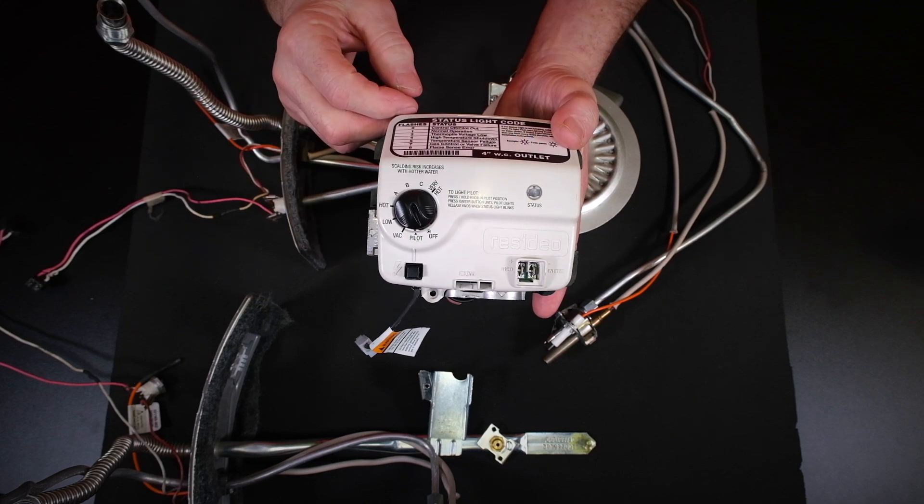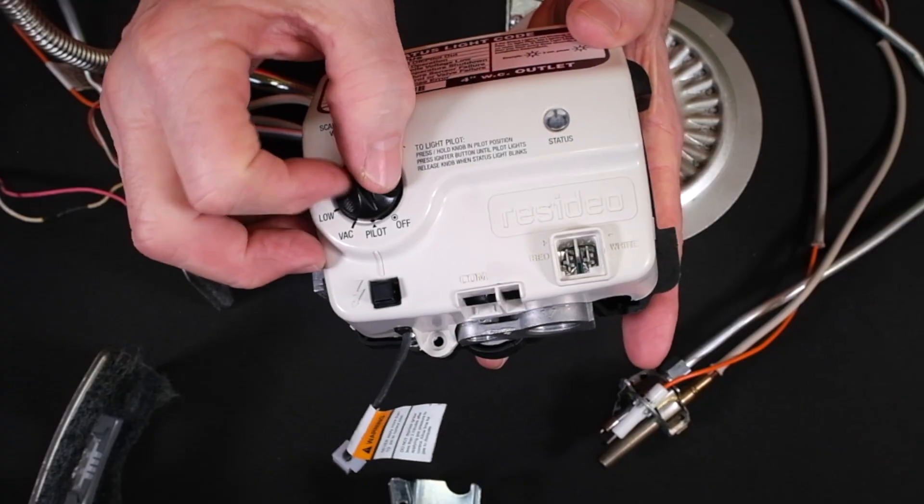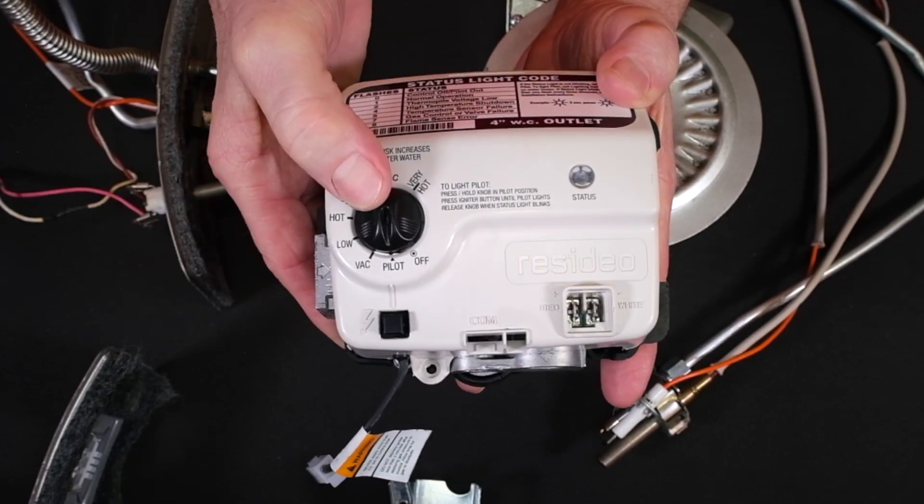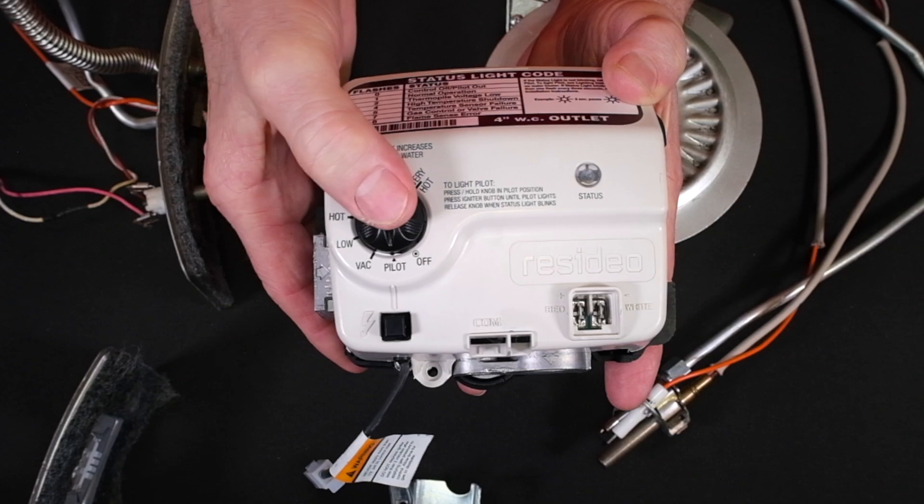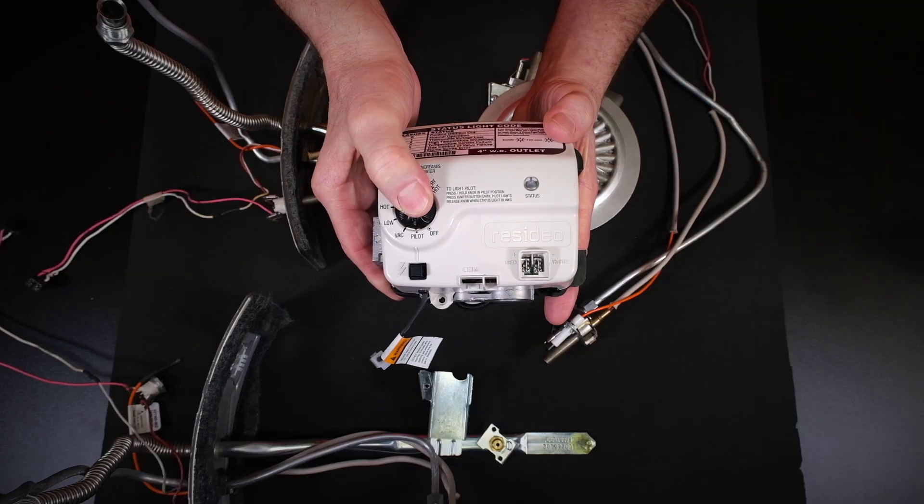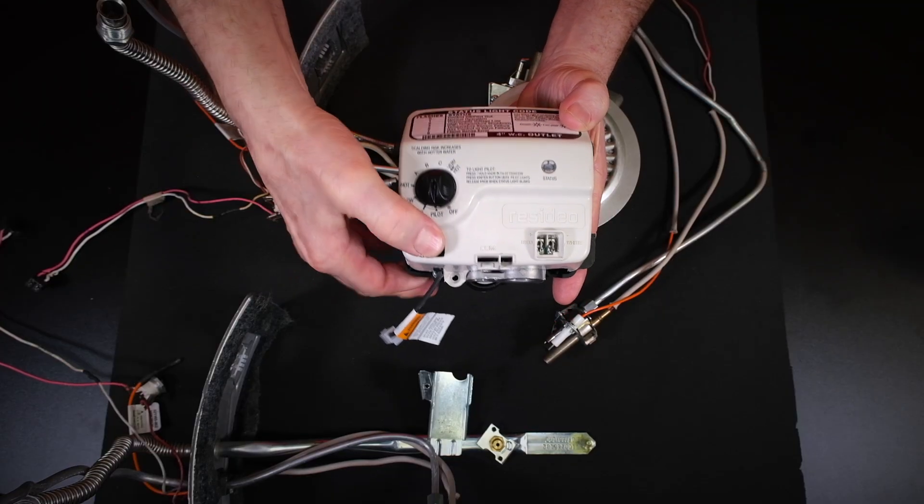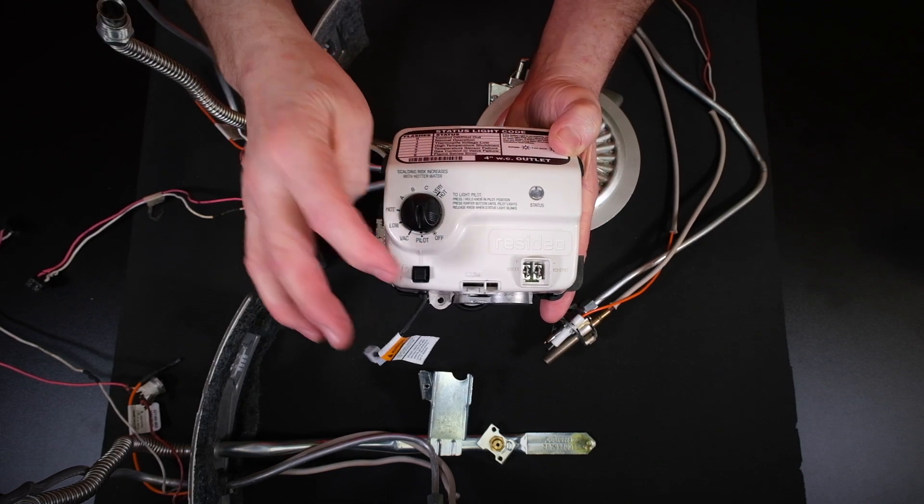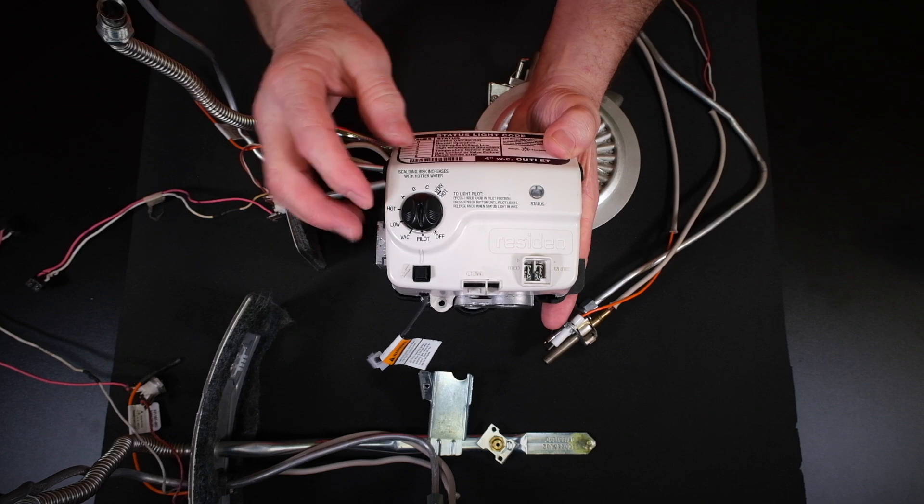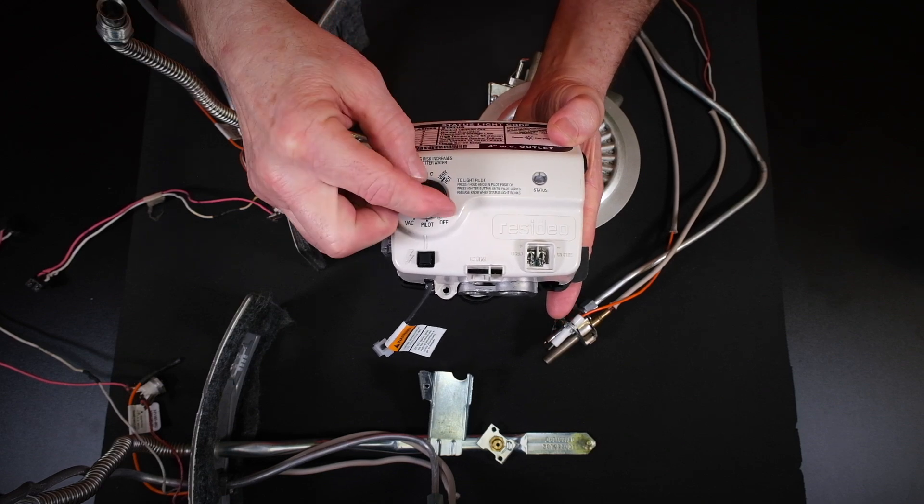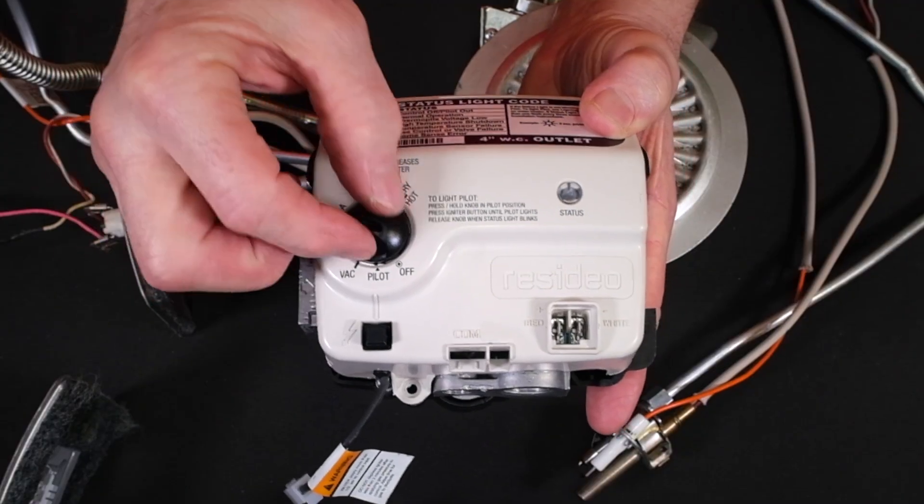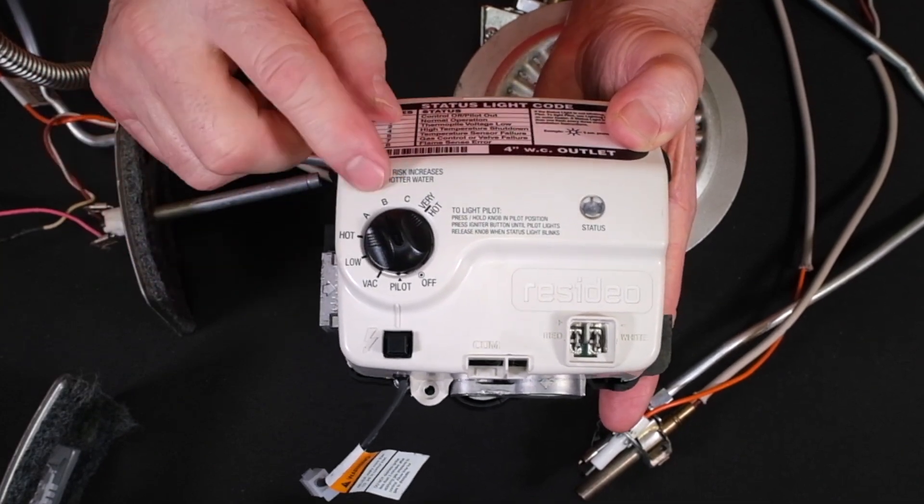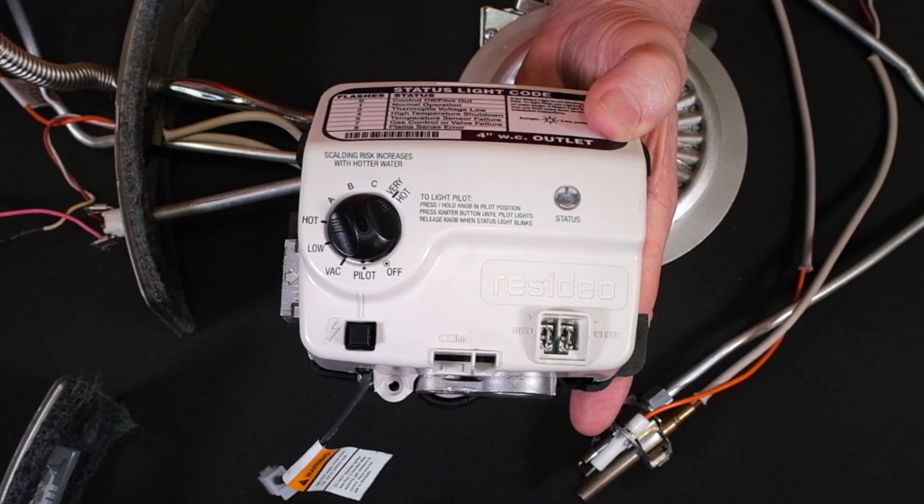Normally it's in the off position when you first get it. In order to light the pilot light, you'll turn it to pilot and this depresses. So you have to push this in, and while you're doing that, you have to press this spark igniter. You want to press that fairly quick. Once it lights, we're going to turn it up to generally between A and B. This is going to run your water somewhere in the neighborhood of 130 degrees.